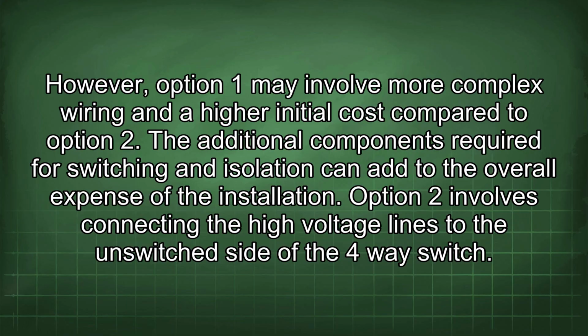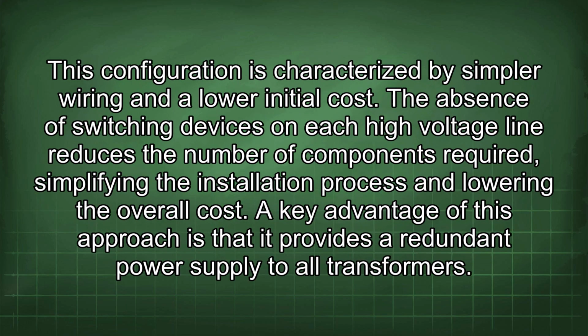Option 2 involves connecting the high-voltage lines to the unswitched side of the 4-way switch. This configuration is characterized by simpler wiring and a lower initial cost. The absence of switching devices on each high-voltage line reduces the number of components required, simplifying the installation process and lowering the overall cost.